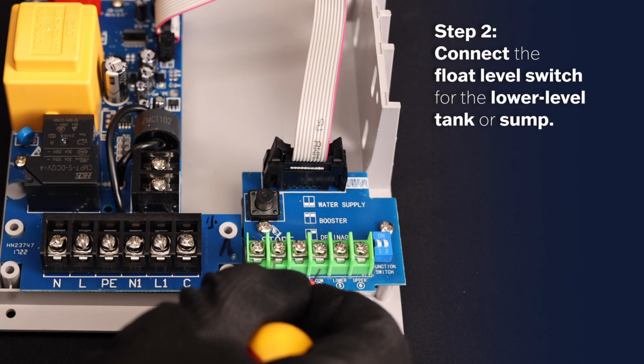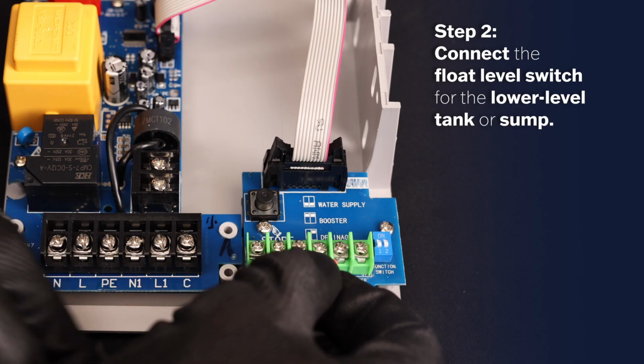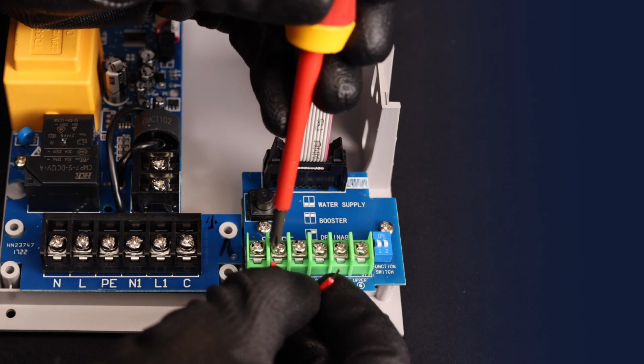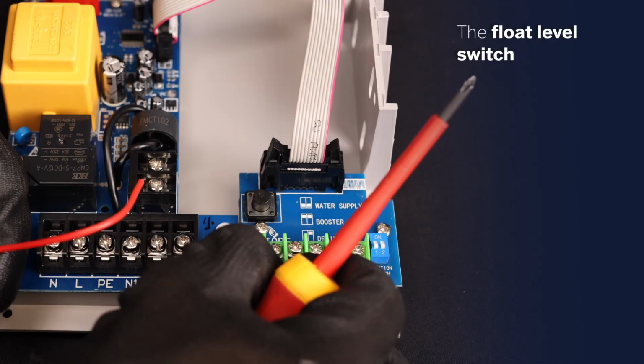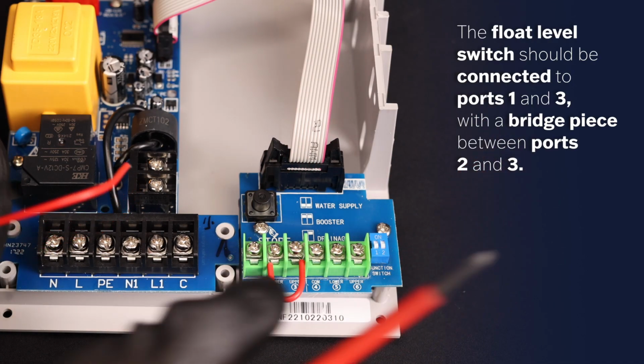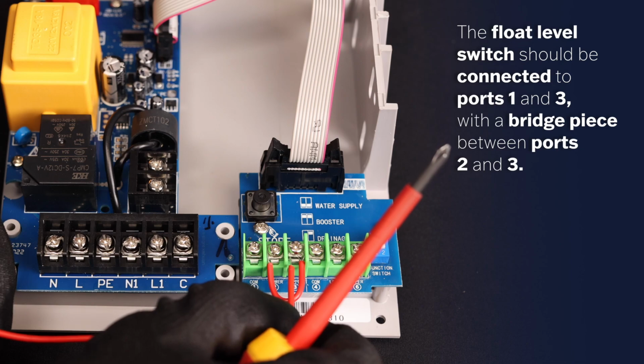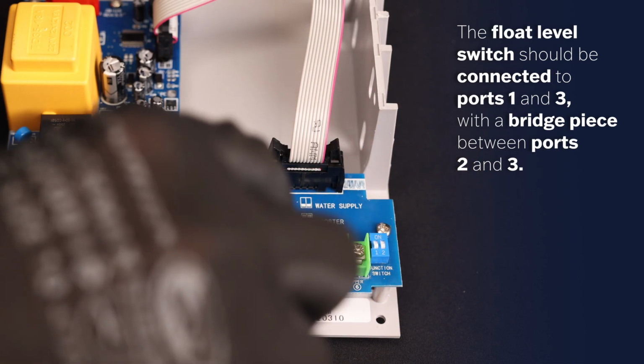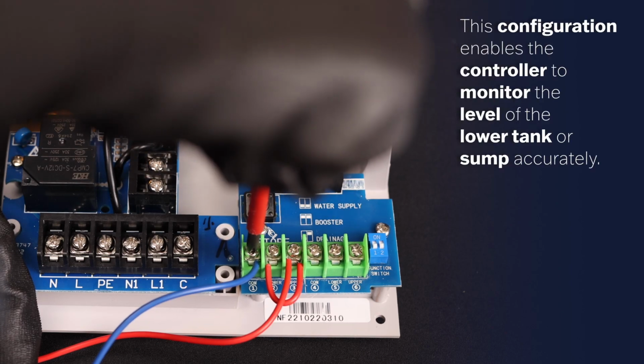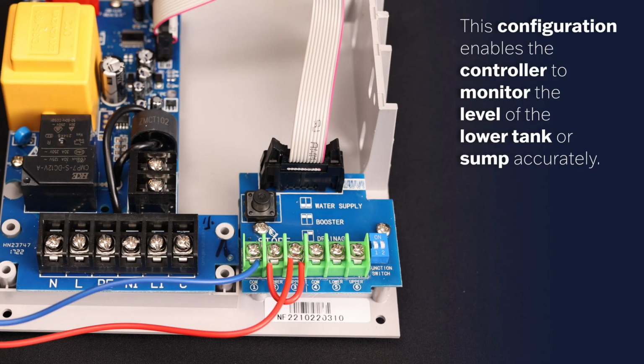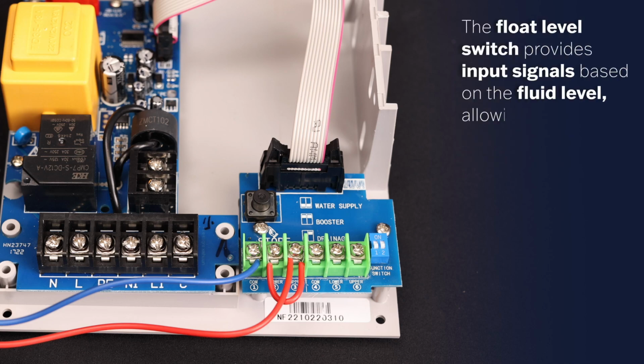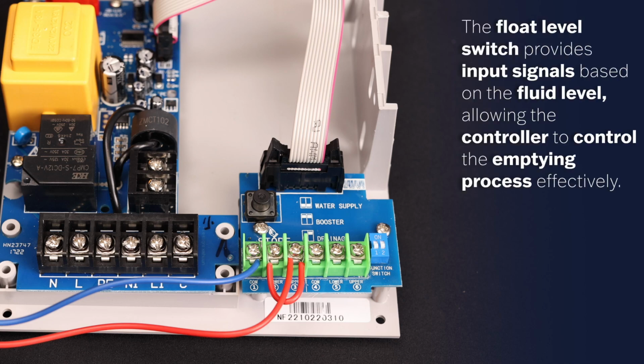Step 2. Connect the float level switch for the lower level tank or sump. The float level switch should be connected to ports 1 and 3 with a bridge piece between ports 2 and 3. This configuration enables the controller to monitor the level of the lower tank or sump accurately.